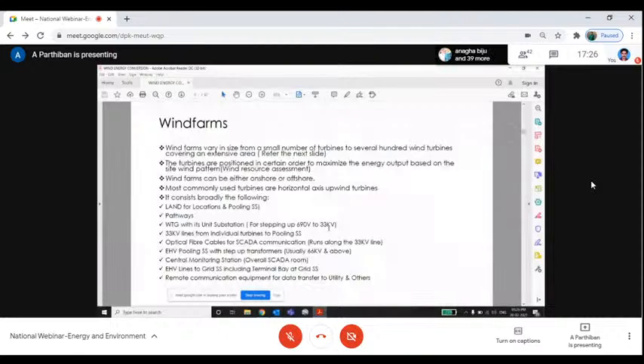which is connected via a 33 kV line, that is an HT line, because the power generated from the turbine needs to be pulled up to the pooling substation. So, for example, it is up to a 33 kV level. This 33 kV level is stepped up to the 230 level at the pooling substation, and from the pooling substation, the electricity is transferred to the grid substation. From the grid substation, the distribution network starts to our houses, our factories, hospitals, everywhere. From the grid substation, the distribution will happen.